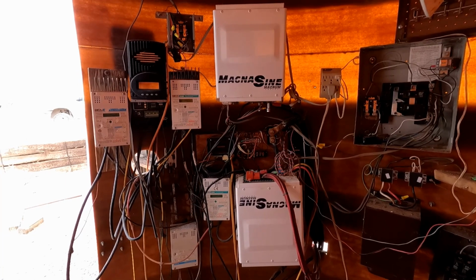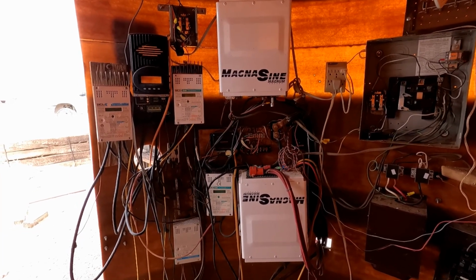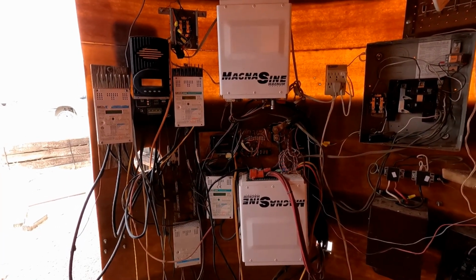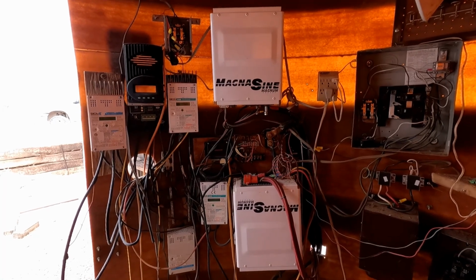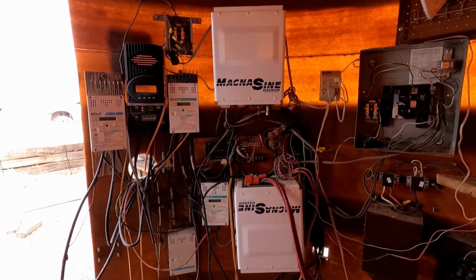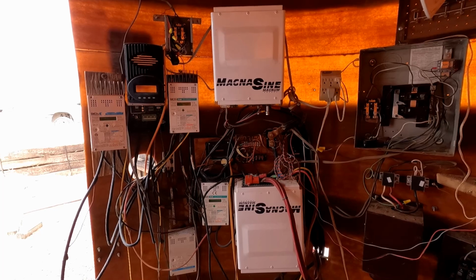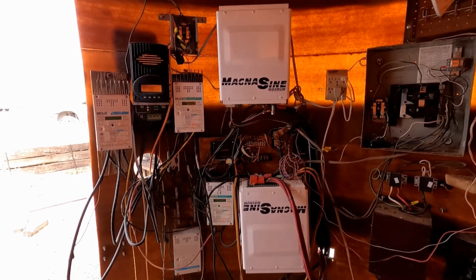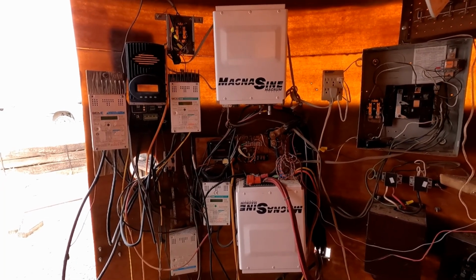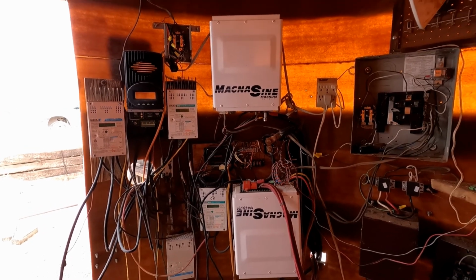When the controller senses the batteries are low or you are commanding it to manually turn on, the inverters are automatically going to switch over when they sense the AC from the generator coming in. It's nice because from the inside of the house it's seamless, you never know what's happened, no interruption of power whatsoever. So you go on generator power.